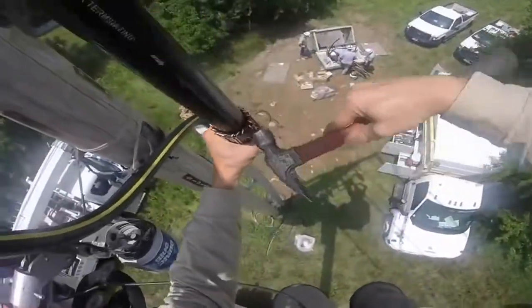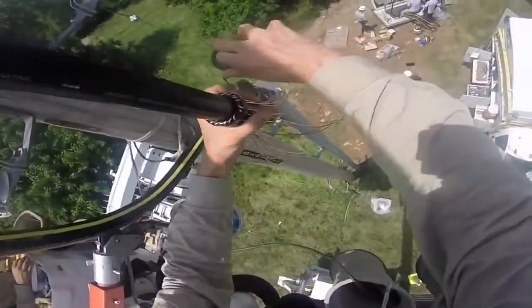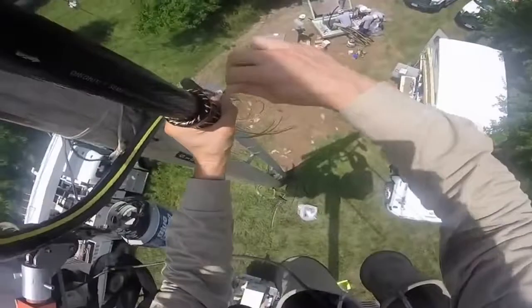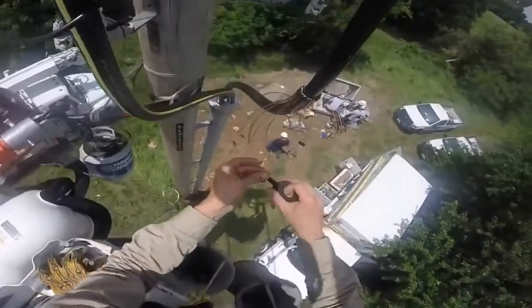Keep them tight. Paul explains: after you bend them down and beat them down, then you do the mastic, then you do a layer of 33 over the top of it. Pull that pretty tight, because when you're pulling that cord, the cord is going to brush up against it and you don't want to knock anything loose.